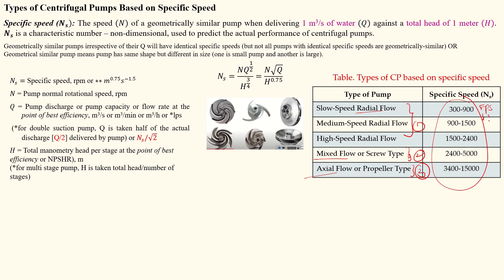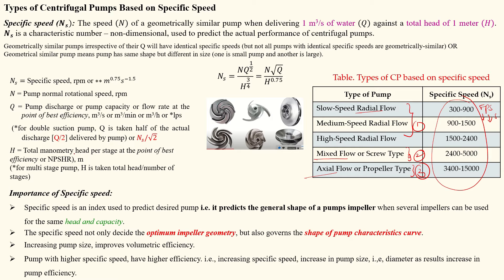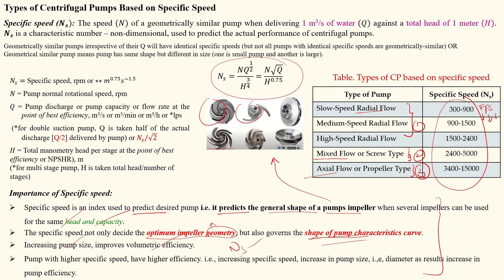The specific speed values shown are in FPS units (foot-pound-second), not SI units. The importance of specific speed is that it predicts the desired pump shape — whether open, closed, semi-open, axial, mixed, or radial — for a given head and capacity. Specific speed not only decides the optimum geometry and size, but also determines the characteristic curve of the impeller. Increasing pump size increases volumetric efficiency, which in turn increases specific speed.